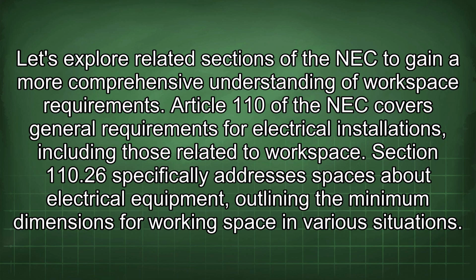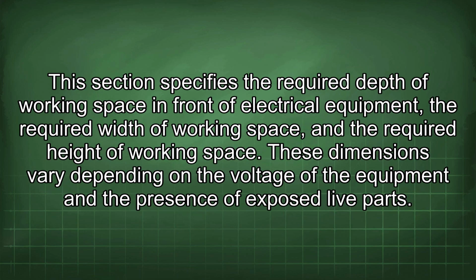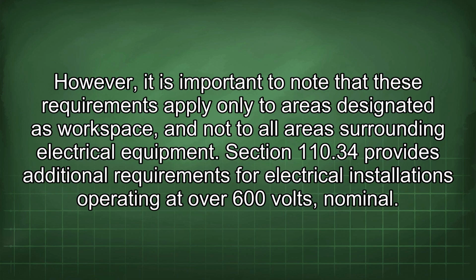Let's explore related sections of the NEC to gain a more comprehensive understanding of workspace requirements. Article 110 of the NEC covers general requirements for electrical installations, including those related to workspace. Section 110.26 specifically addresses spaces about electrical equipment, outlining the minimum dimensions for working space in various situations. This section specifies the required depth of working space in front of electrical equipment, the required width of working space, and the required height of working space. These dimensions vary depending on the voltage of the equipment and the presence of exposed live parts. However, it is important to note that these requirements apply only to areas designated as workspace and not to all areas surrounding electrical equipment.